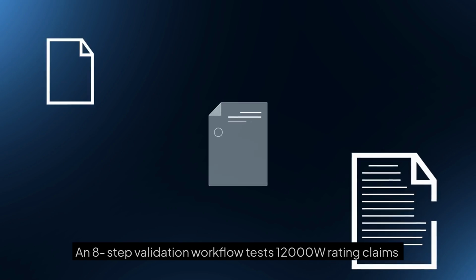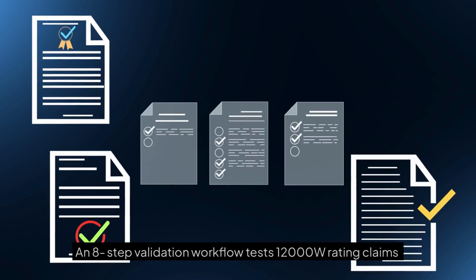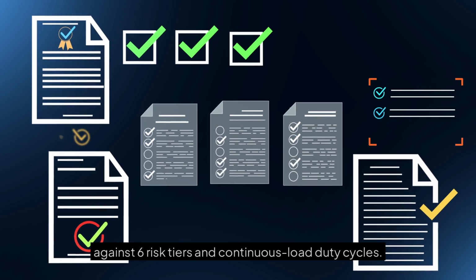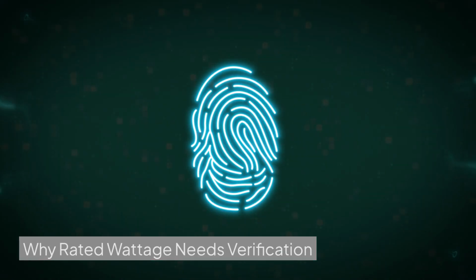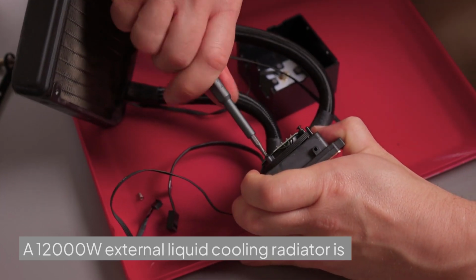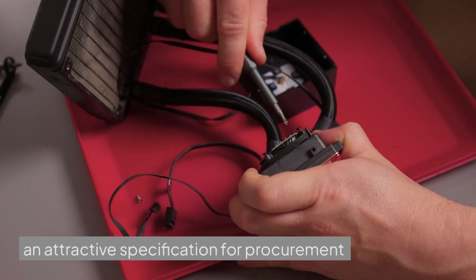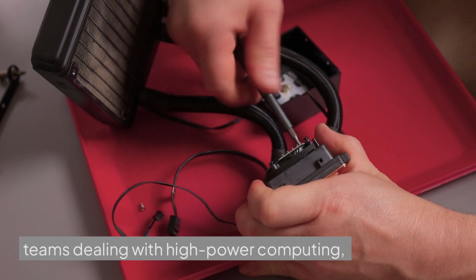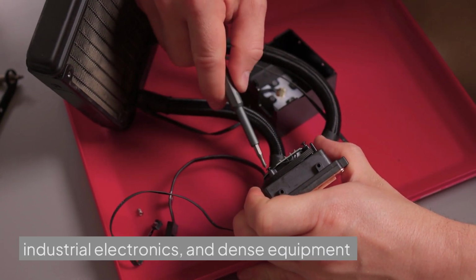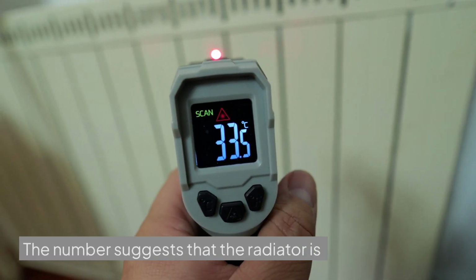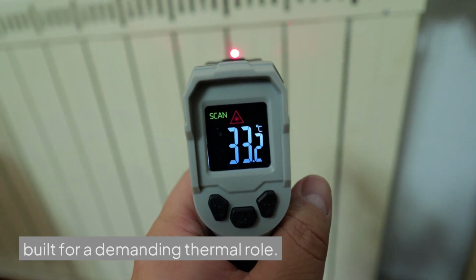An 8-step validation workflow tests 12,000 W rating claims against 6 risk tiers and continuous load duty cycles. Why rated wattage needs verification? A 12,000 W external liquid cooling radiator is an attractive specification for procurement teams dealing with high-power computing, industrial electronics, and dense equipment layouts. The number suggests that the radiator is built for a demanding thermal role.